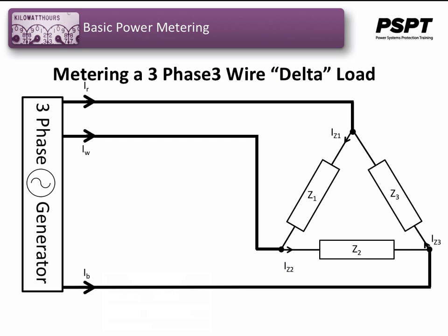Metering a 3-phase 3-wire delta load. The delta load is made up of 3 individual loads connected phase to phase, as shown in this slide. This time we are labeling the phases RWB, or red, white, and blue. To meter the load, we would use 3 watt meters or a 3-element watt meter.